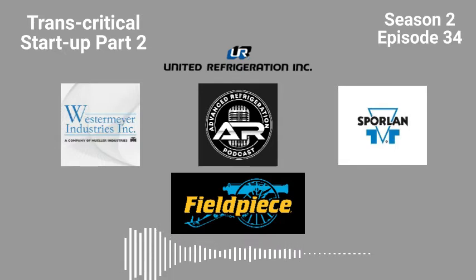Then your load management on the back end is a nightmare because when they come out of defrost, you come out guns blazing with an EPR and a freezer. If it's not managed, you end up with a bunch of nuisance proof alarms. Getting that low temp set up and bringing it down slowly is important. When you have a store like a Trader Joe's or Aldi where you don't have a lot of load, until you get that freezer box pulled down, you're pretty much SOL. Those compressors are going to cycle — it is what it is.